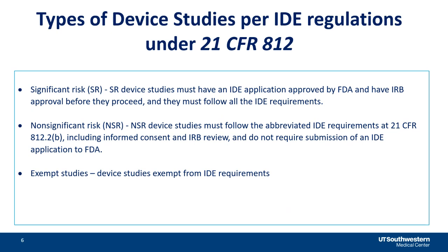The IDE holder is considered the sponsor and must follow requirements outlined by the FDA. Research involving a non-significant risk device is slightly different, but still must follow what is referred to as abbreviated IDE requirements under 21 CFR 812.2b.